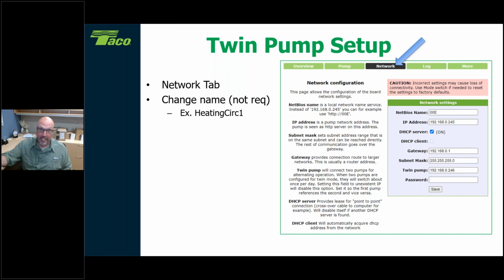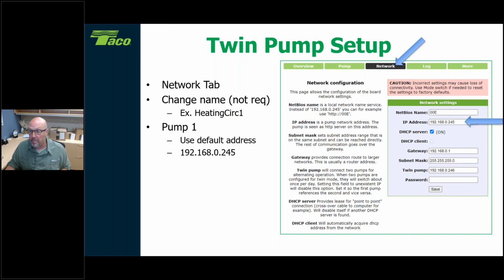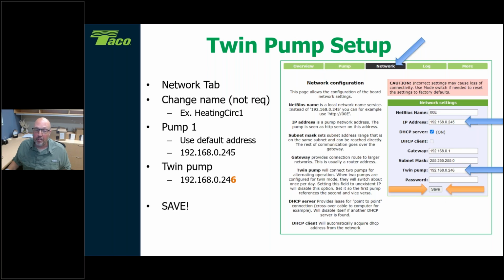Obviously you're disconnecting the Cat 5, so you've got to take that Cat 5 out of it so you can see that pump and log into it. Remember, pump one has that 245, that's your IP address listed here. When you want to talk to a second circulator, you come all the way down to the tab that says twin pump, and you type in 192.168.0.246 is my suggestion. You could put anything you want there. I would just make it 246, or you can make it 244, whichever one is your second circulator. Probably go 246 because you just count the numbers going upwards. And then make sure you hit save. Again, make sure you hit save.